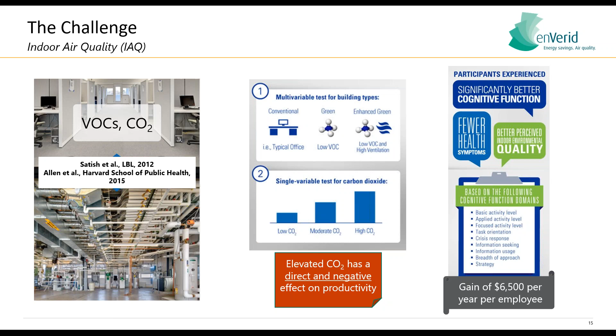So the enVerid technology solves these three challenges, energy saving, outdoor air quality, and indoor air quality, by using a performance-based approach to indoor air quality procedure documented in ASHRAE Standard 62.1, plus air cleaning. What does it mean? It means we are implementing air cleaning as an energy efficiency measure, so less ventilation is needed to maintain the same acceptable indoor air quality. You implement both dilution, so you need less dilution, plus air cleaning, and you maintain the same indoor air quality. One indirect benefit is that you decrease the intake of outdoor-generated pollutants indoors.